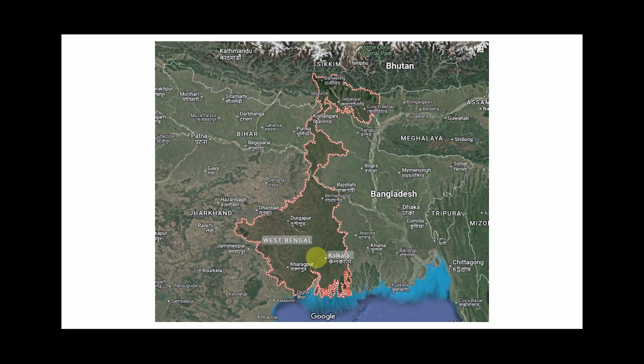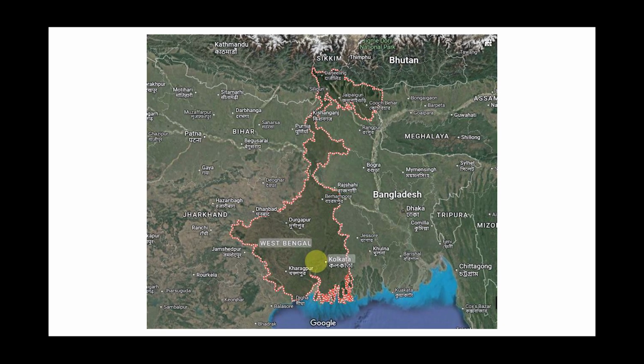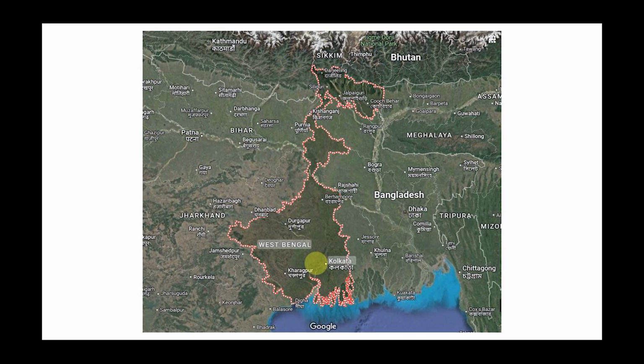But inadvertently, the SIM procured was 4G Kolkata circle. All the instruments were located under the West Bengal circle. The system was not working. There was no data transfer. In this context, let me say the network provider has one circle for the state of West Bengal and another for Kolkata, the capital of West Bengal.